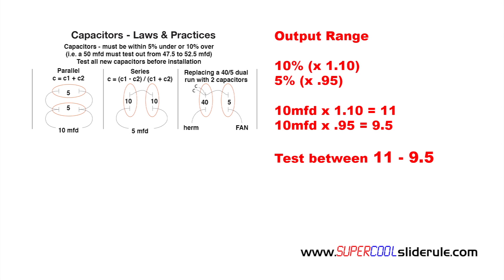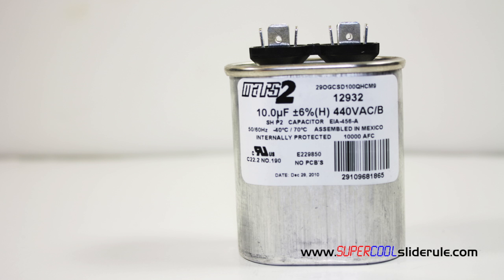Many people have heard that a capacitor can be tested with an older analog tester looking for a spike. Please save yourself the trouble and do not use this method. Also, a capacitor should be smooth and uniform on the top and sides. If there is any bowing or bulging evident of any kind, the capacitor is bad and must be replaced.